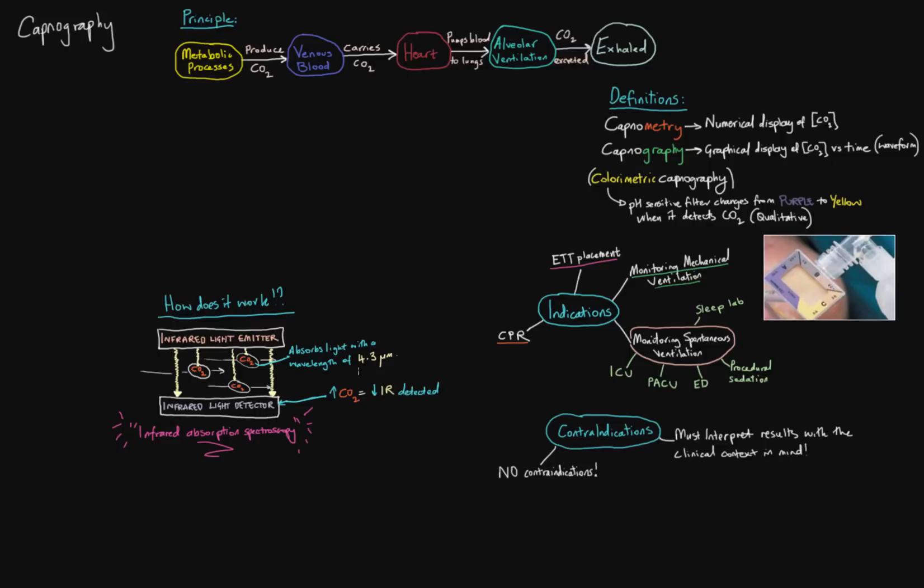Now CO2 will absorb this wavelength of light. So the more CO2 is passing through your detector, the less of this light that is emitted is going to get picked up by your detector. So if you know how much light you're emitting and you know how much you're detecting, you can therefore deduce how much CO2 is absorbing whatever the difference is. That's the basic principle, and this is the most common way that CO2 detectors are working nowadays.